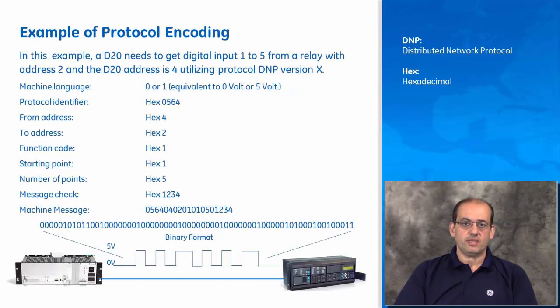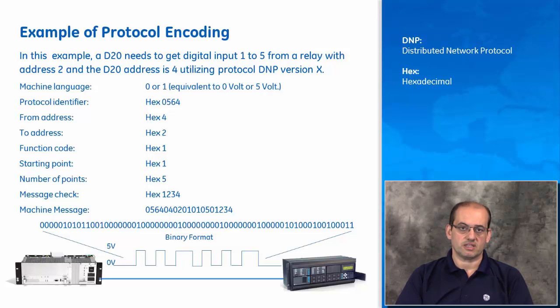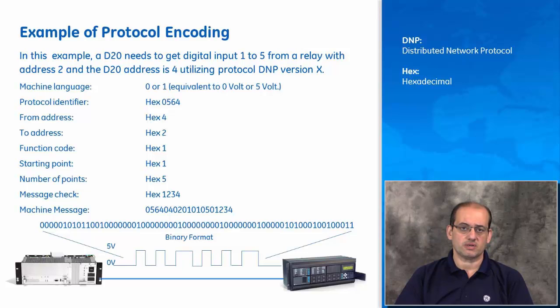In a substation with two devices — one acting as a master, like a D20 communicating to a UR relay — the D20 needs to get digital inputs one through five from a relay with address two, and the D20 address is four, using a preferred communication protocol. Let's say it's DNP protocol version X. I'm using an oversimplification of a DNP protocol because the real DNP protocol contains many features, as we'll explain later. This simplification helps our learning to understand how a protocol impacts messages transmitted between one IED and another.